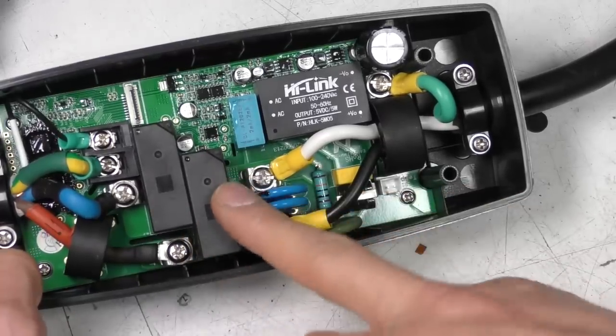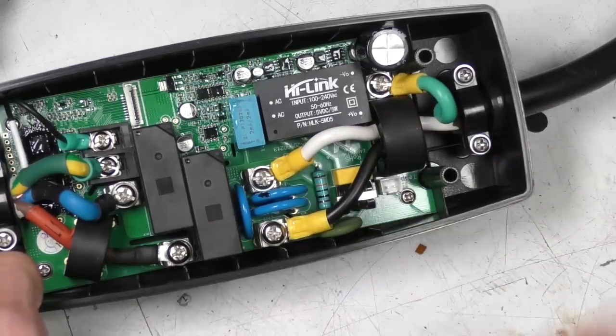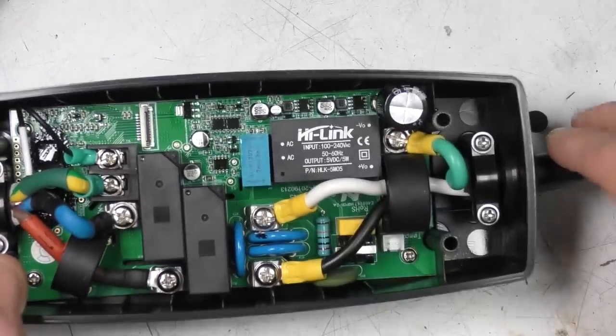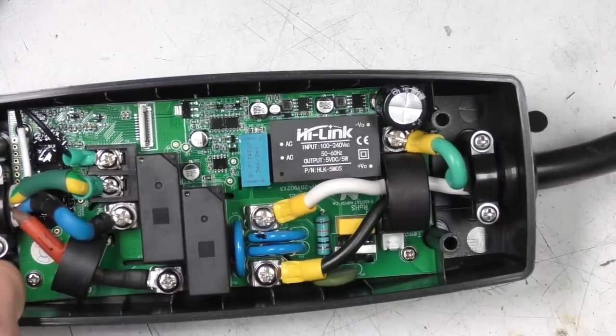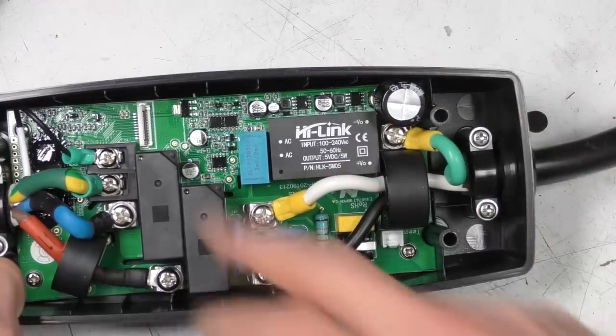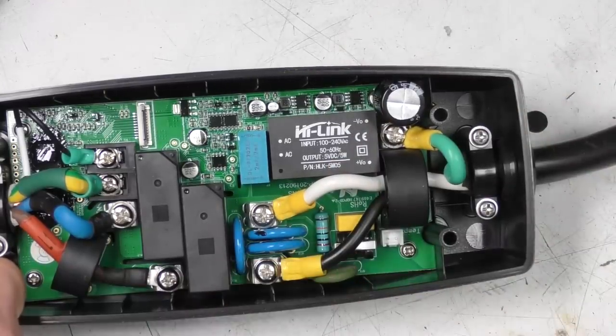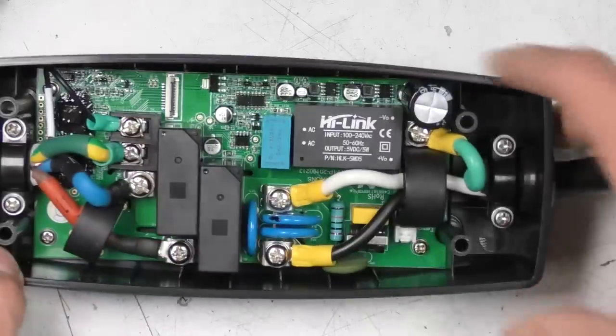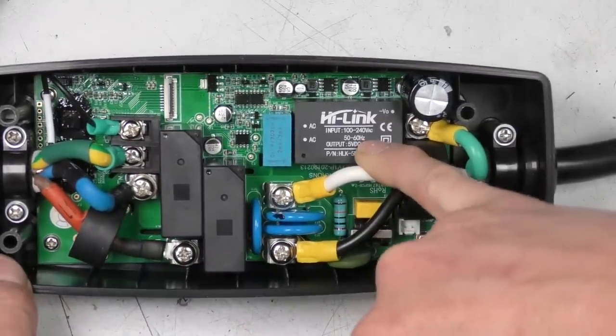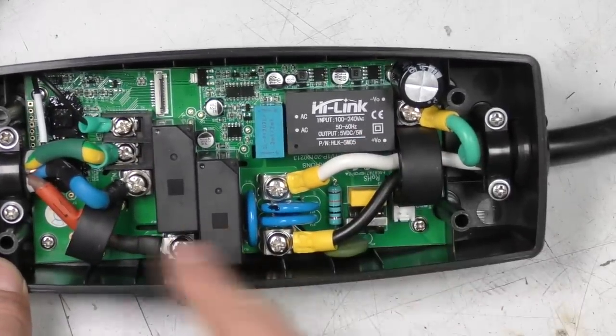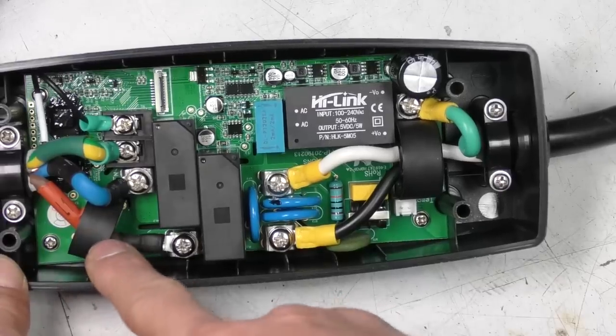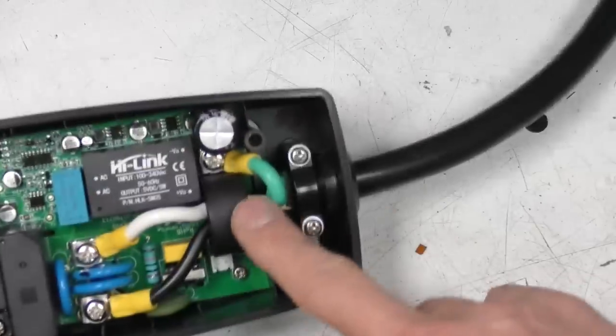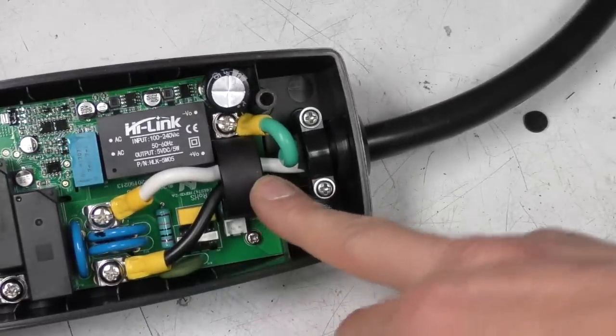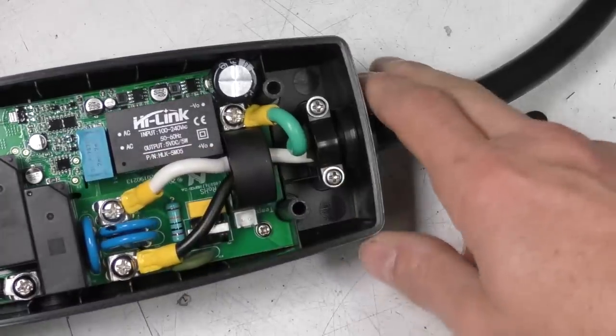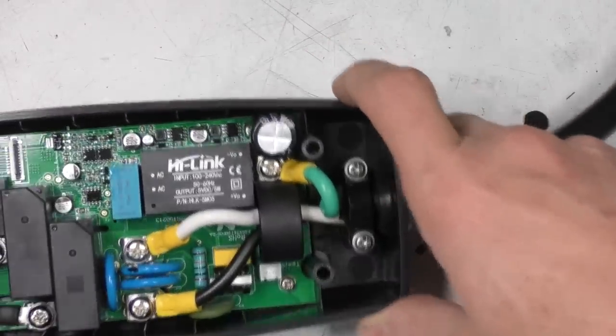Obviously a 50 amp relay is going to have fairly chunky mechanical parts, so a non-latching relay will probably need quite a lot of current to hold it in, which would just contribute to internal heating because the power dissipates in the coil. So in here we've got a little modular switch mode power supply, 2 relays, the current measurement transformer there, and then the leakage sensing transformer here. So everything's on one PCB. There is some conformal coating on the board to give a certain degree of moisture resistance.